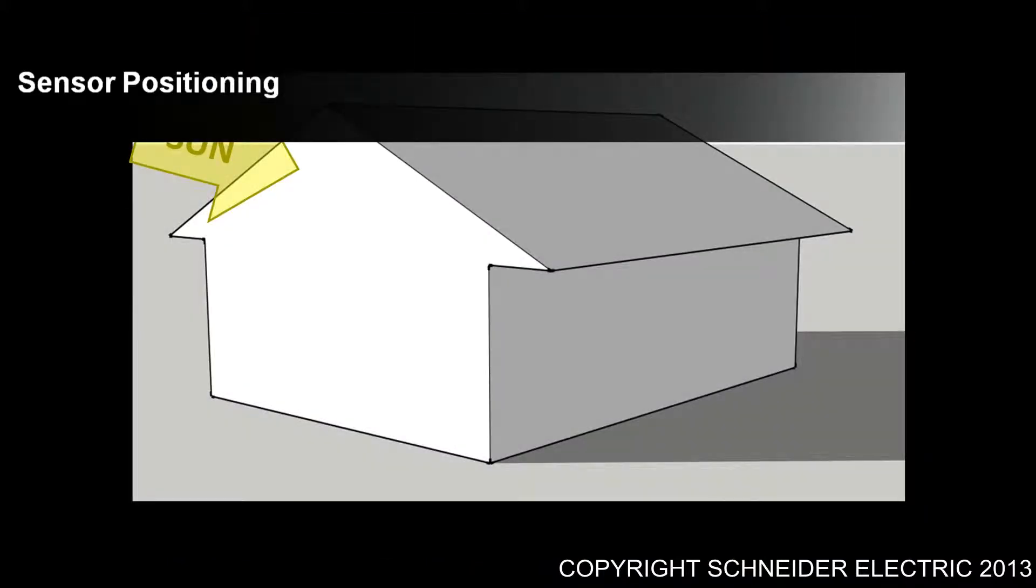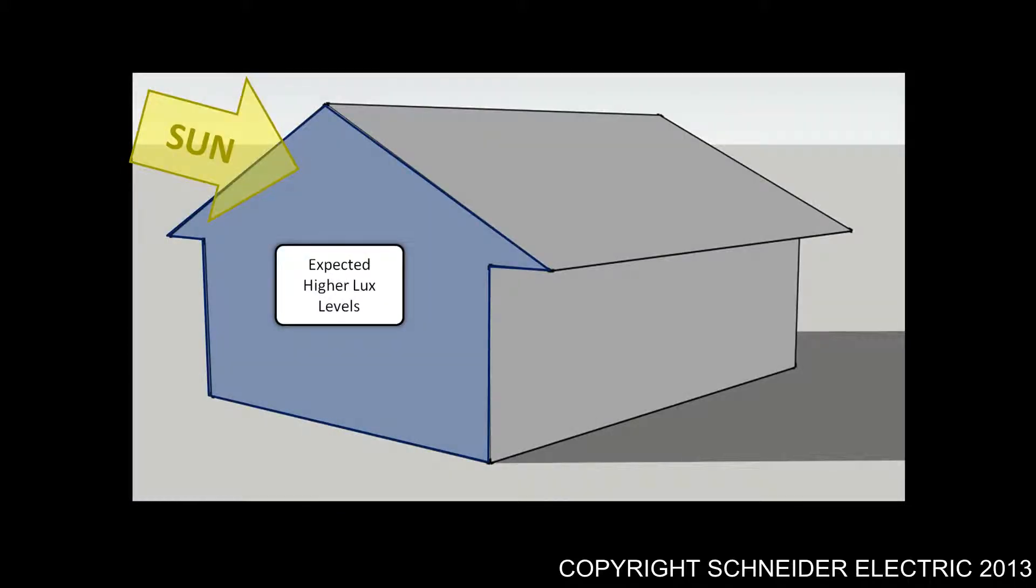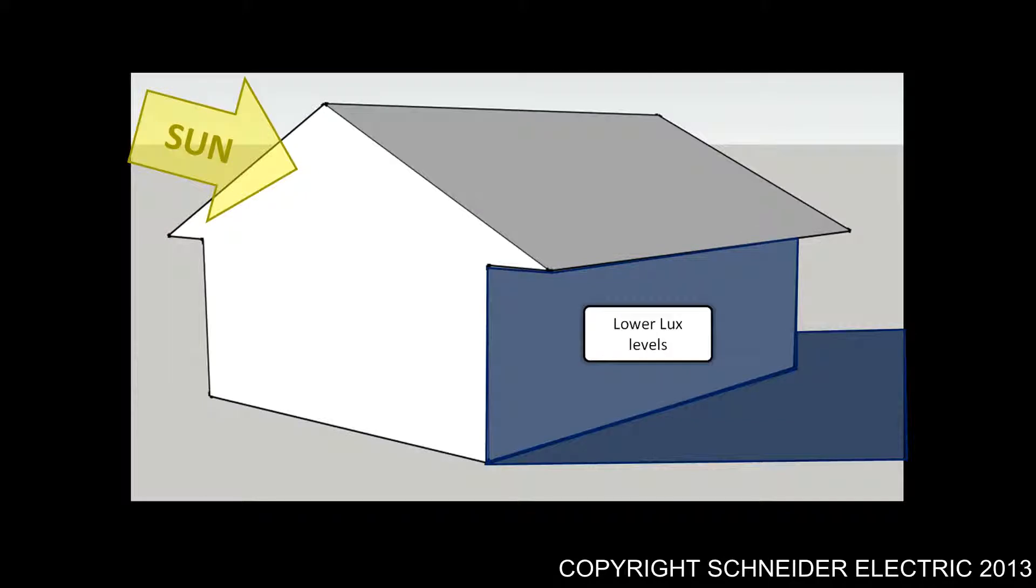Another thing to take into consideration when installing these sensors is sensor positioning. There's this misconception that if you install sensors outside, they're all going to have the same lux level. That's not necessarily the case, because if you've installed sensors where they're going to be exposed to sunlight, you're going to have to set those particular sensors at a higher target lux level than those areas that aren't exposed to the sun.